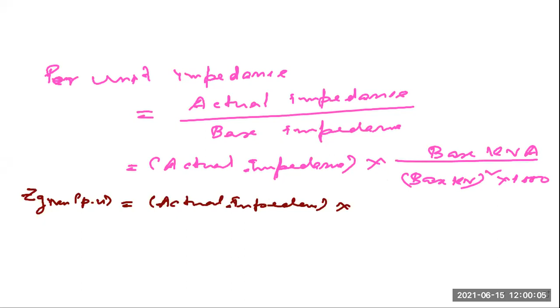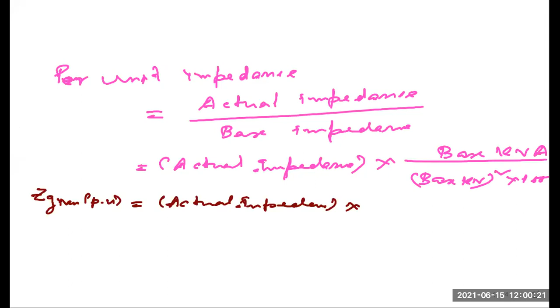We have two quantities: given and new. So Z given per unit equals actual impedance into base kVA given, divided by base kV given squared into 1000. Similarly, Z new per unit equals actual impedance into base kVA new, divided by base kV new squared into 1000.